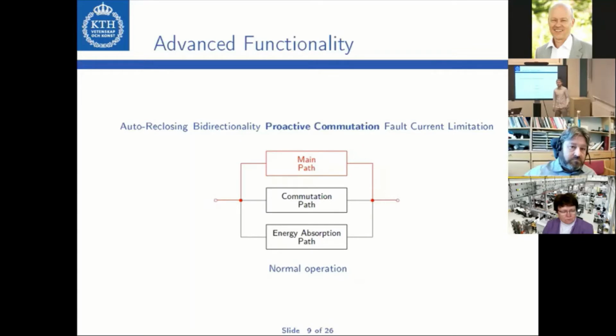An interesting capability is the proactive commutation mode. In this case, the DC circuit breaker commutates the current to the commutation path before the DCCB is tripped, already when it internally determines that this could be a critical condition. If the DCCB is then tripped at a later point, the delays of this protection delay can be compensated, which then speeds up the interruption process. However, it could turn out that the DCCB is never tripped, and then the DC circuit breaker must at some point decide that this was not a fault, and it has to commutate the current back to the main path to resume normal operation.